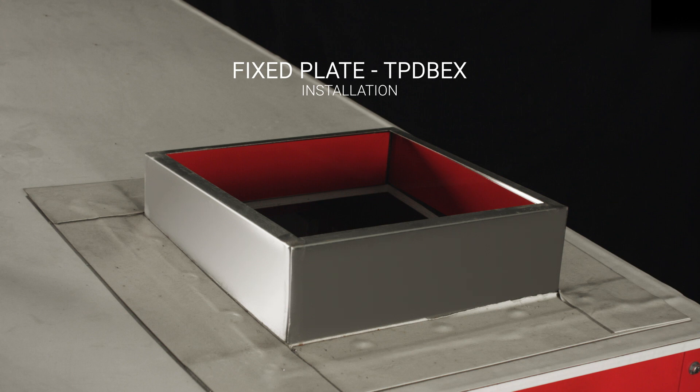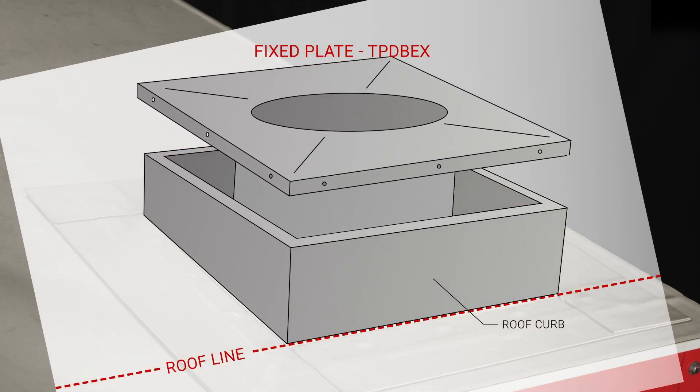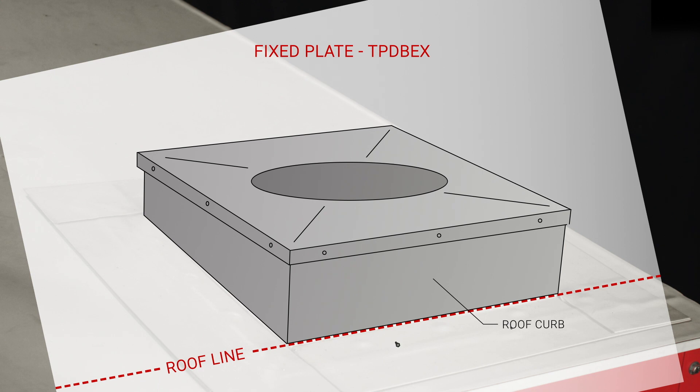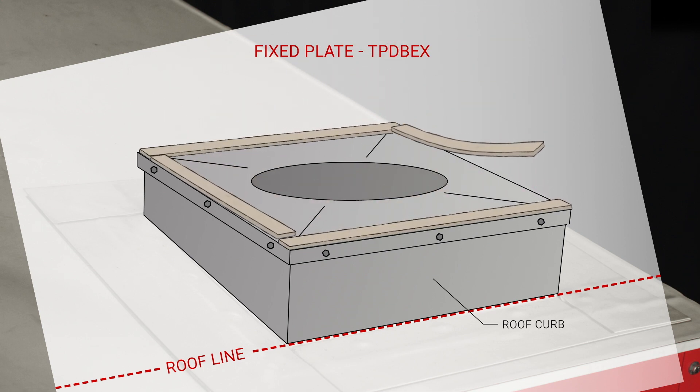To install a fixed TP DB EX plate, first place it on the curb. You can then secure the plate to the sides of the curb using three self-drilling fasteners per side. Lastly, add gasket material to the edges of the plate as shown.